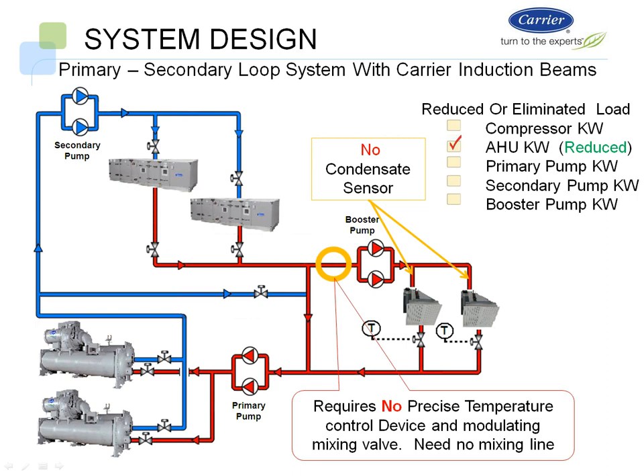And then if you look at that same system, sensible only, with the new Carrier induction beam units, again, in a sensible only application, which they work fine in, you do get all those benefits on the reduction in the air handler. But what you also get now is you don't have to worry about that three-way valve or a plate frame heat exchanger or a boiler induced into there, because if your water temperature every once in a while may get colder where you potentially can have condensation, these units have a 2-inch drain pan, and that's a dual sloped and pitched drain pan. So even if they were going to get a little water in them, they would dry out, and you have that safety there.